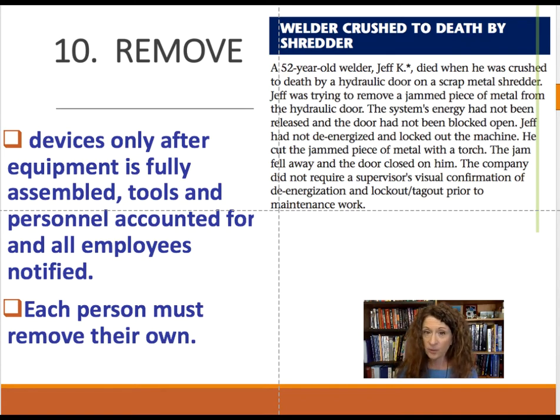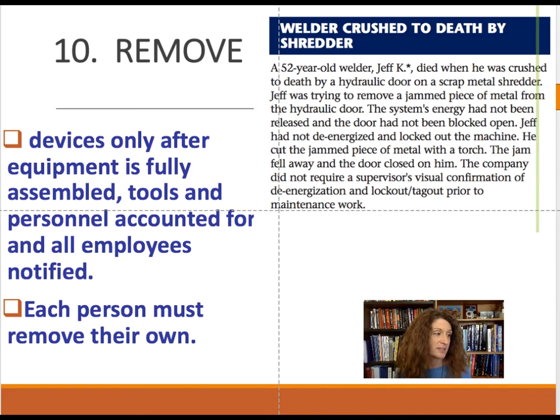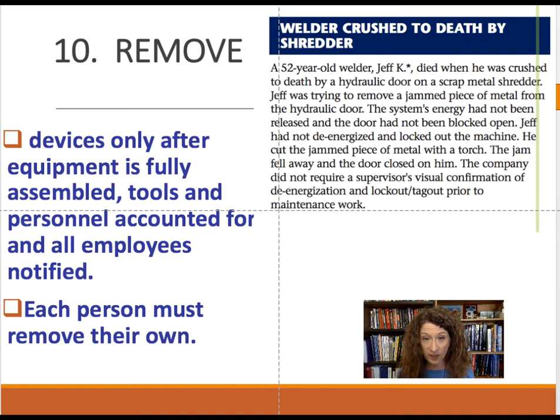A 52-year-old welder named Jeff died when he was crushed by a hydraulic door on a scrap metal shredder. He was trying to remove a jammed piece of metal from the hydraulic door, but the system's energy had not been released — it was turned off, but the door still had energy in the pistons. Jeff had not de-energized and locked out the machine. He cut the jammed metal with a torch, the piece fell away, and the door closed on him. The company did not require a supervisor's visual confirmation of de-energized and locked-out equipment prior to maintenance work.